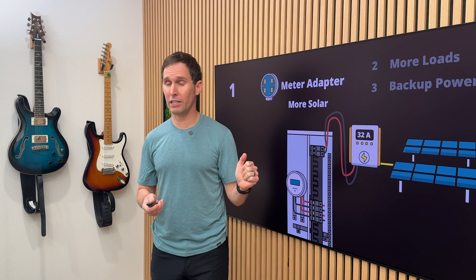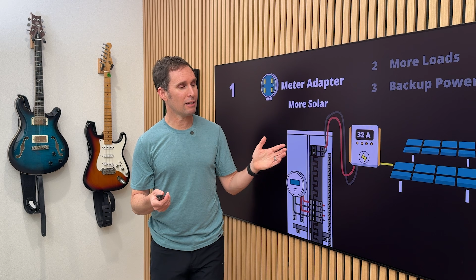According to the National Electric Code, you can only backfeed up to 120% of the bus bar minus the main breaker. So to say it straight, if you haven't got a lot of training on how you can backfeed electricity and how much, there is a substantial limitation. There are new ways around that with new technologies like power control systems, but in general, backfeeding is only allowed at a certain level, a certain threshold.